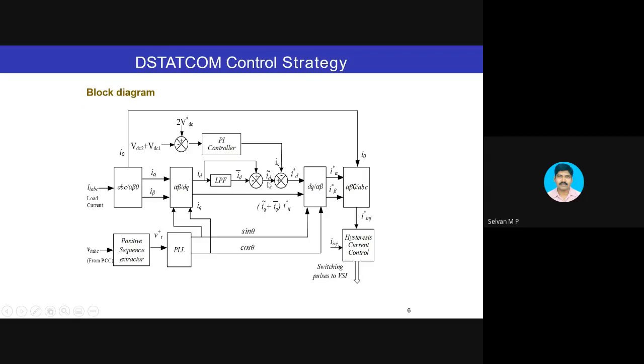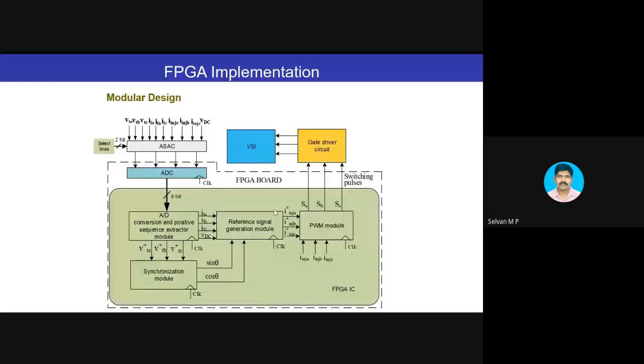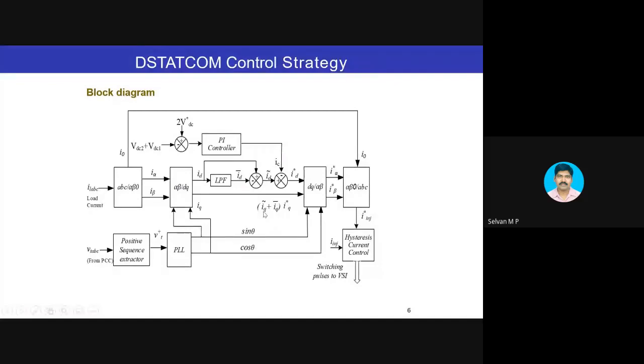If there is no harmonics, then no problem. I need not worry about the D component. The Q component is the complete Q component, the reactive power drawn by the load, as well as the harmonic component, which is present in the Q component, has to be supplied by the D STATCOM. So this Q component is completely taken.